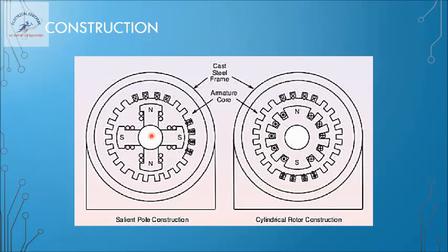In the cylindrical rotor construction, also called smooth cylindrical rotor or non-salient rotor, instead of having separate protruding structures there is a drum-like structure. The entire drum is wound by windings, making it a two-pole magnet, though four-pole, six-pole, or eight-pole versions are also possible. DC supply is given to the rotor, so it acts like an electromagnet with north and south polarities.